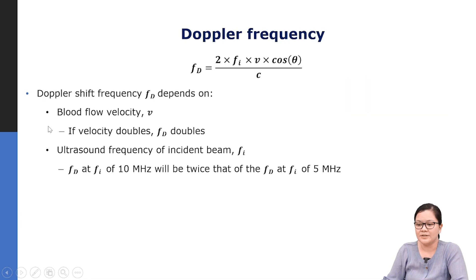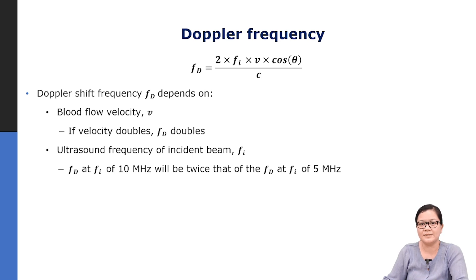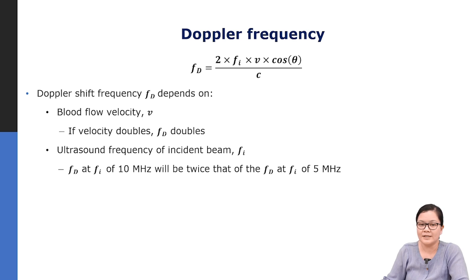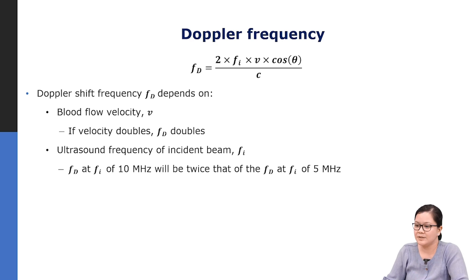The Doppler frequency shift depends on several factors. It is proportional to blood velocity: if the velocity doubles, the Doppler frequency shift doubles; if halved, the shift halves. The ultrasound frequency of the incident beam also affects it — the Doppler shift frequency is proportional to the incident beam frequency. So if the incident beam is at 10 MHz, the Doppler frequency shift would be twice that produced by a 5 MHz incident beam. Similarly, halving the incident frequency halves the Doppler shift frequency.